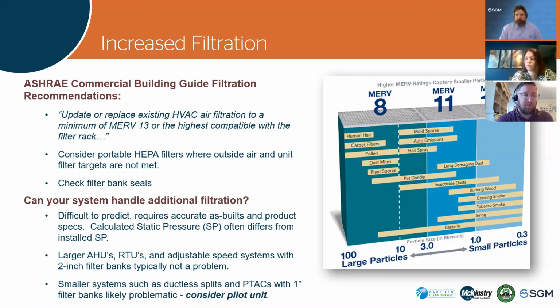There's a question on what do we look at to know if our systems can handle this increased filtration? And it's surprisingly difficult to predict this. You need accurate as-builts, not design drawings. Those are helpful though too. And accurate product specifications, the original documentation. And the reason for this is we calculate a static pressure drop during design, and it so often differs from what we actually experience when it's installed. So it's a tough one to predict.